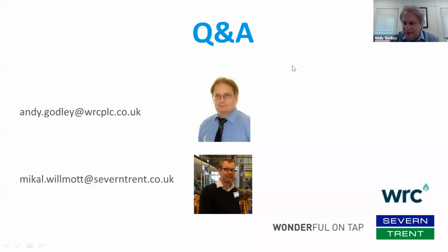I don't know whether you've got anything to add to that, Michael. No, I think that's a really good and complete answer, Andy. And as you say, we know mechanical meters are going to wear, aren't they? They've got more wearing parts than perhaps the clamp-on ultrasonics or the electromagnetic meters. With something like a clamp-on ultrasonic, you need to make sure it's still got a good connection after a few years. And again, there's been a real good improvement on the clamp-on ultrasonics over the last few years on how well they perform, and also ensuring that you have the right pads or whatever connection you need onto the main.